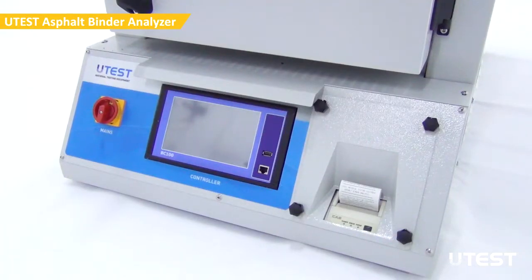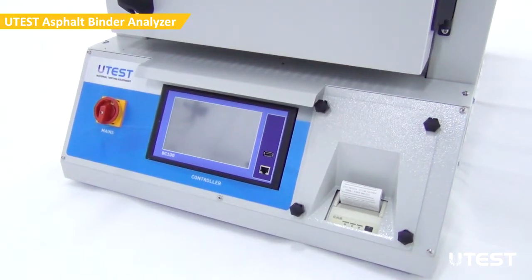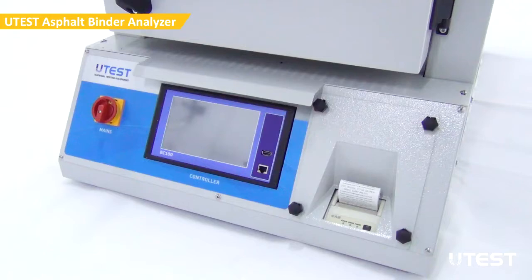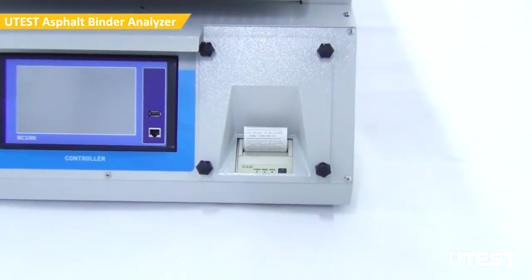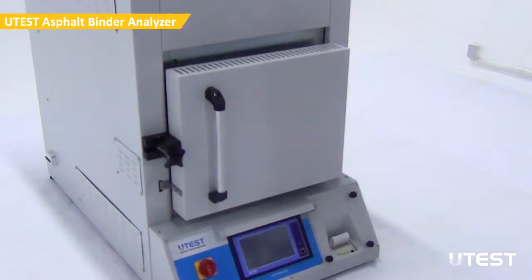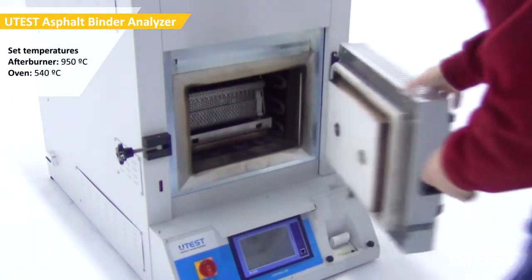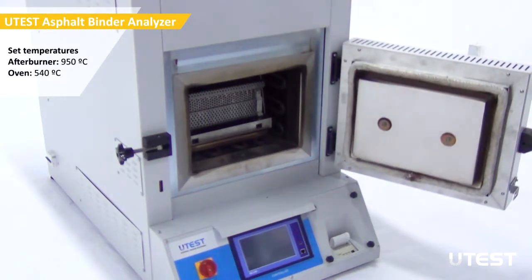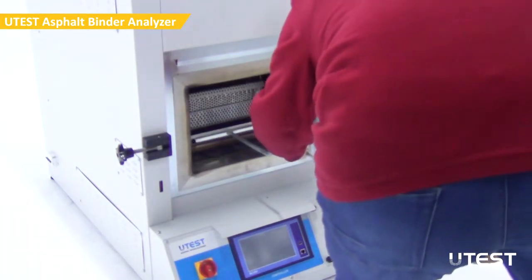The TFT Touchscreen Controller displays test data such as temperature and sample weight, and controls test parameters during the test, while the permanent memory stores test results. The device is also equipped with an onboard serial printer, automatic door locking system after 180 degrees Celsius, and a high efficiency heating system with after-burner chamber for total combustion of exhaust fumes to minimize emissions and conform to EU directives.